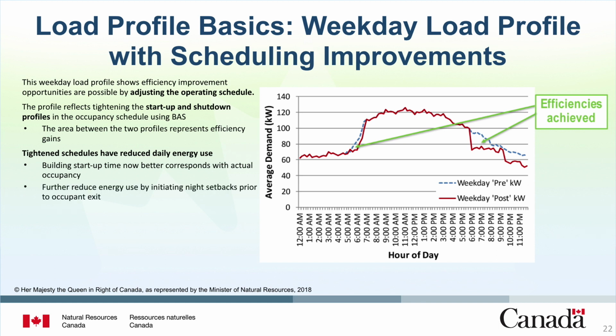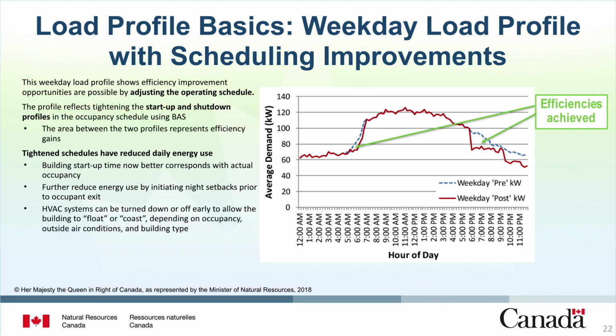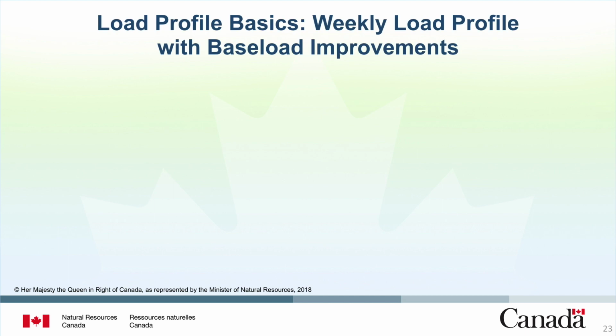To further reduce daily energy use, building night setback can be initiated prior to the scheduled occupant exit. HVAC systems can be turned down or off early to allow the building to float or coast, depending on occupancy, outside air conditions, and building type. Load profiles can also be used to reduce base load.